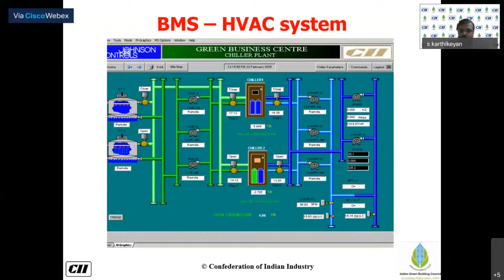The last aspect is commissioning. Many times we select very efficient equipment and an excellent control system, but the building or equipment may not operate as efficiently as perceived at the time of design. There could be many reasons for this between the time of installation and operation.